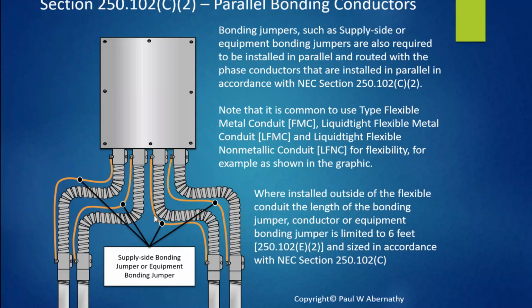Or this could be done on the load side, same kind of configuration, and these would be what's called equipment bonding jumpers. And in that point, it's bonding over. And in doing this, you're going to size it based on 250.122, based on the size of the overcurrent protective device supplying the conductors that are within this cable assembly, all right, or conduit. All right, so I drew this image because I wanted to show you both ways that you're dealing with it.